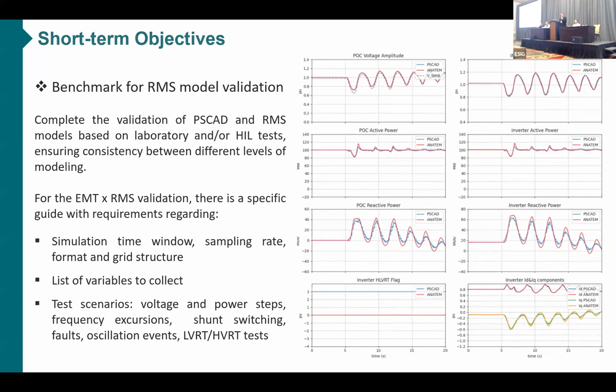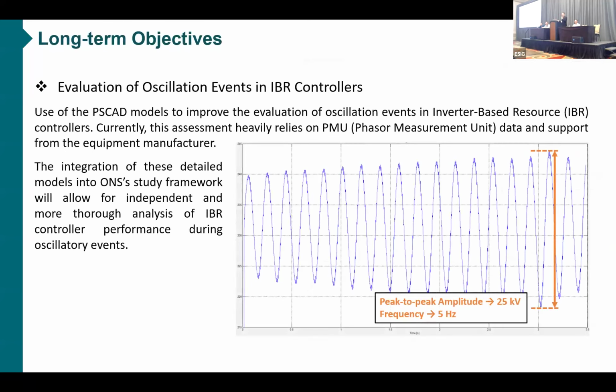Okay. And then we go to the long-term objectives. One of them would be to use these PSCAD models to improve evaluation of oscillation events in IBR controllers. Right now this assessment is based purely on PMU data and support from the equipment manufacturer. So we can pretty much only use the PMUs that we have to pinpoint the location and the generator that is originating the forced oscillation. And then we depend totally on the manufacturer to analyze what's happening in that plant.